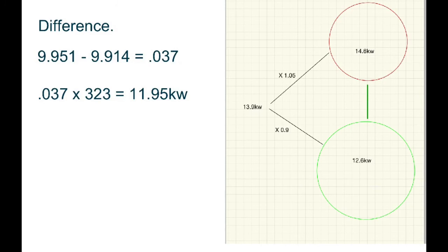If when we gas rate the appliance it's outside of those two figures, outside of that range, then it isn't working correctly. And this time when we worked it out, it was 11.95, which is below 12.6. So we know that the cooker was not working correctly.